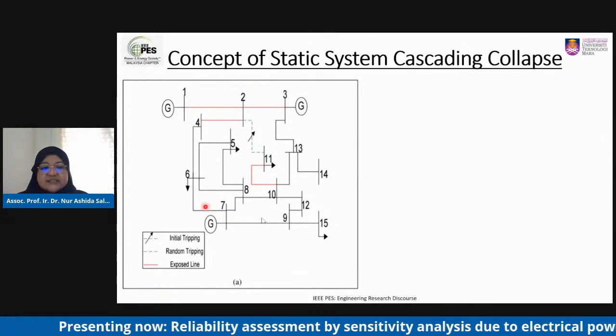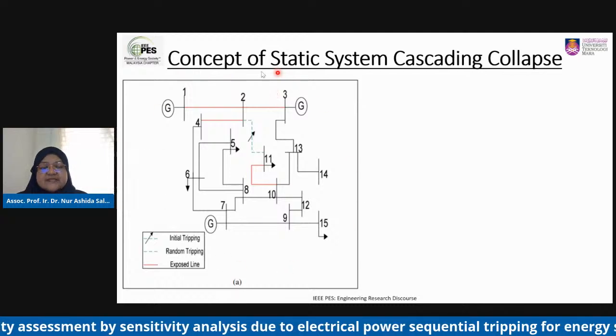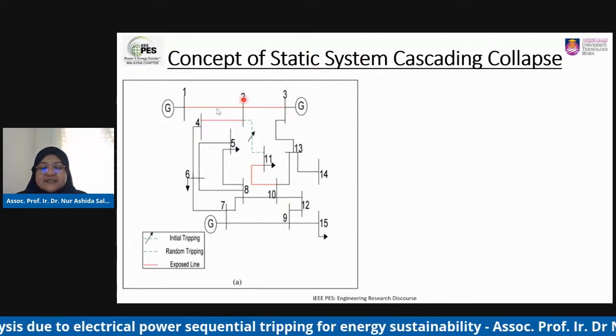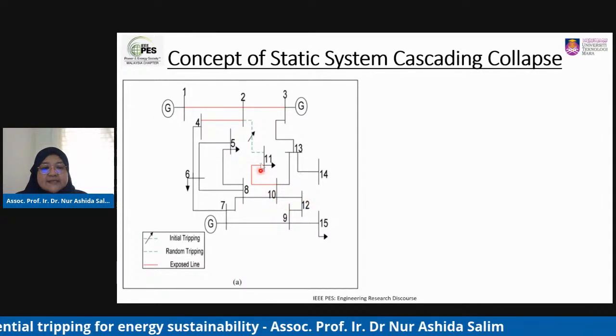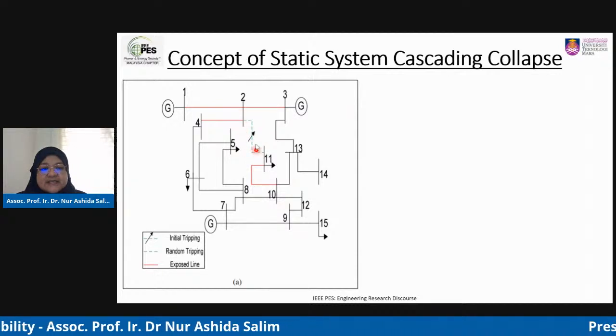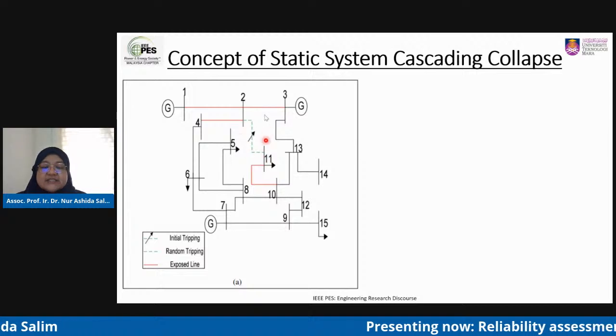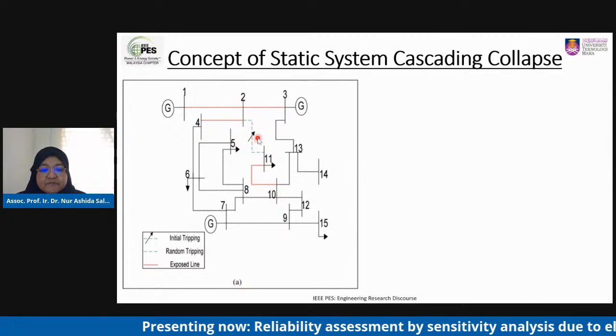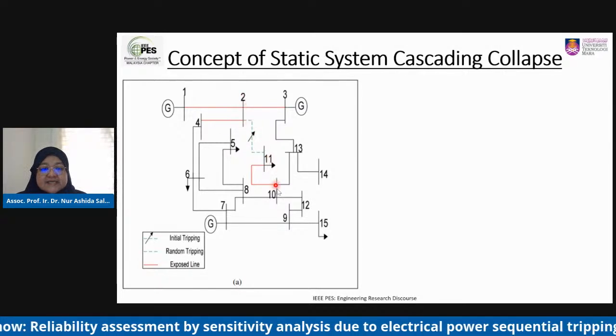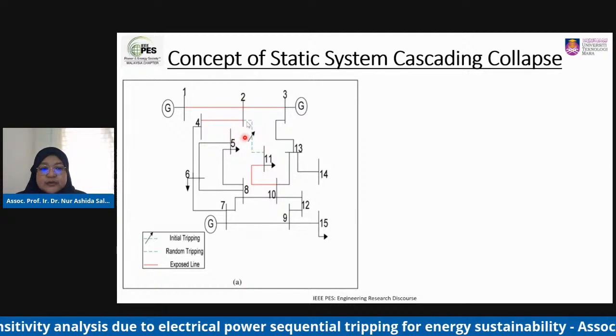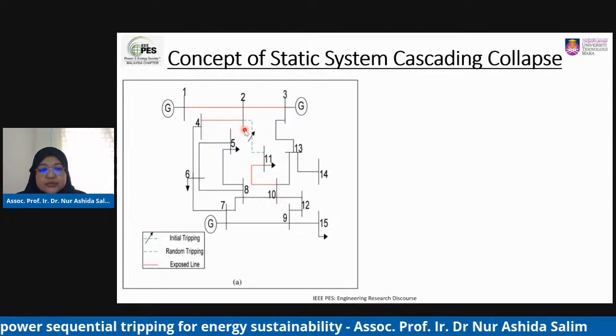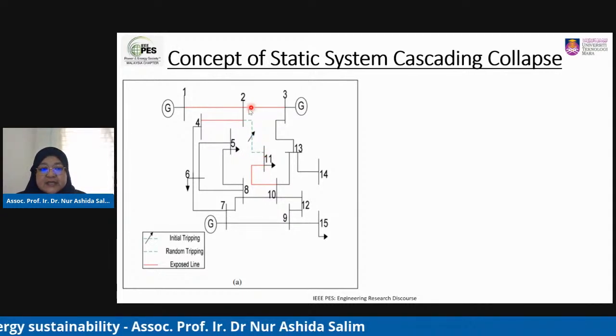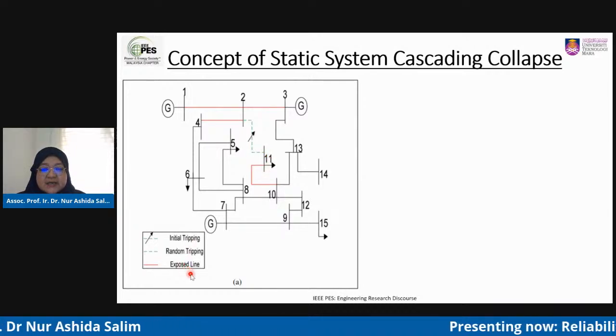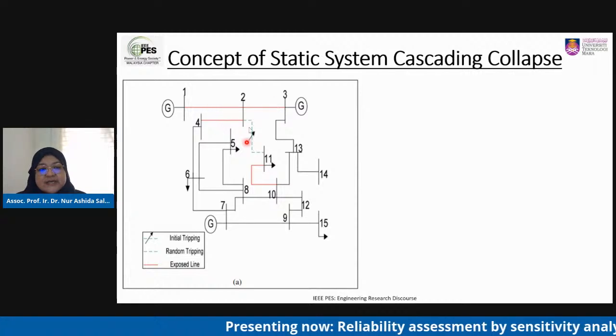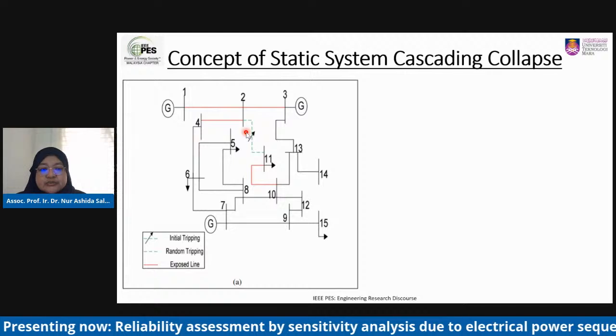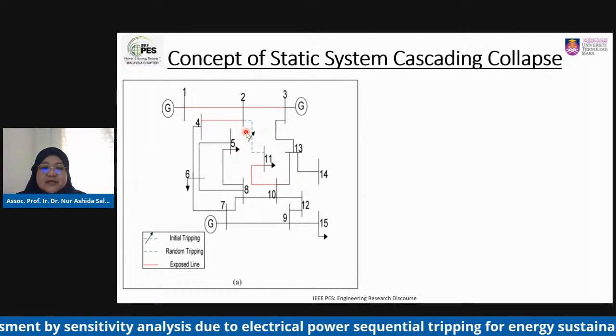This is just a fixture system where I have selected the transmission line connected from bus 2 to bus 11 as the initial tripping line. Let's say this particular line trips; the lines connected to the same bus as the tripping line will compensate the load for the tripping line. That means at bus number 2 and bus number 11, all the lines connected to these buses are called exposed lines — meaning these particular lines connected to the initial tripping line will have the probability to trip next, and subsequently trip another line.